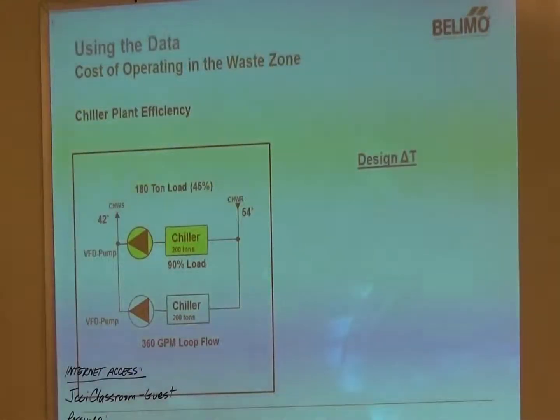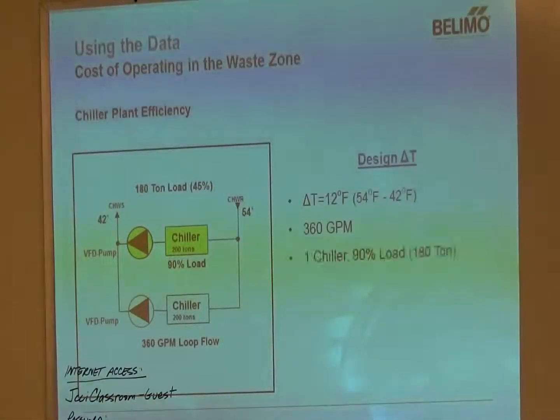Now looking at the cost of operating the waste zone, using a bunch of pressure dependent valves. Here we've got a 180 ton load. We've got a couple different chillers. We've got one chiller loaded up at 90%. Each chiller can handle 200 tons, so we've got a 180 ton load. We're good. The flow in the loop is 360 GPM. Our design delta T is 12 degrees at 360 GPM. Like I said, we've got the one chiller loaded at 90%.